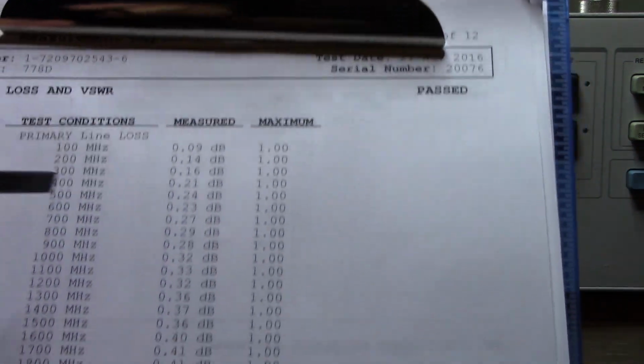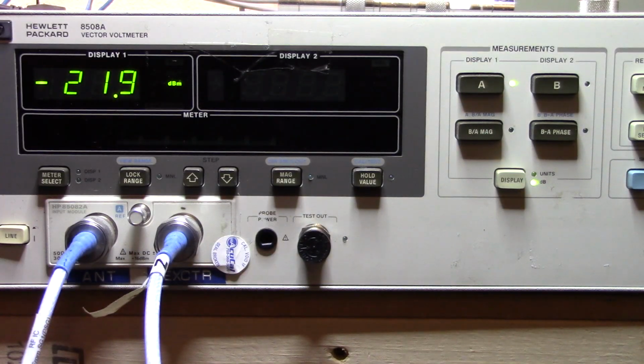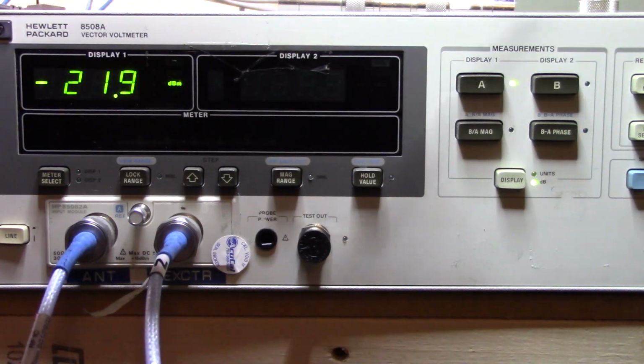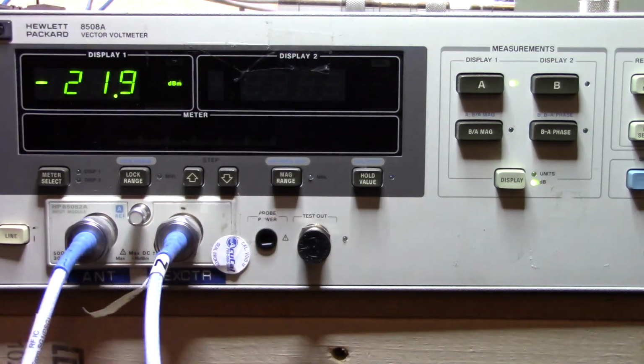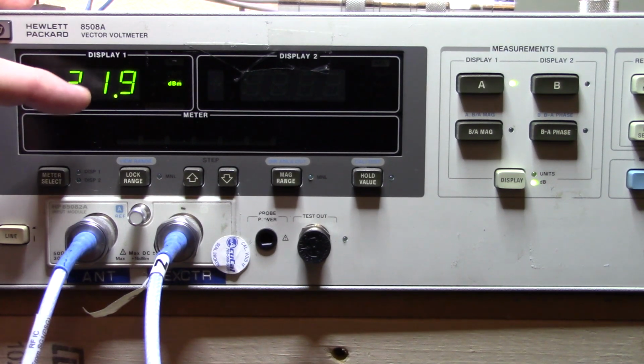Yeah. So what you can see here is this is actually a test of the directional coupler. And if you were using this in a real test environment, you'd know exactly what the frequency and how much am I losing on the transmission line, on the strip line through it. What is the incident at that frequency? Really, it's going to be minus 21 instead, or minus 20.4 or something. Right. You'd be able to take that and add that to your specs or to your measurements, if you wanted to do it that way. So what we're showing here is that we're at minus 21.